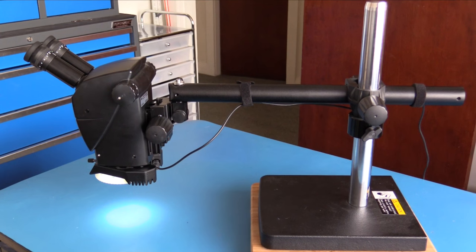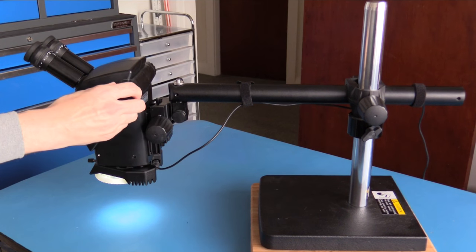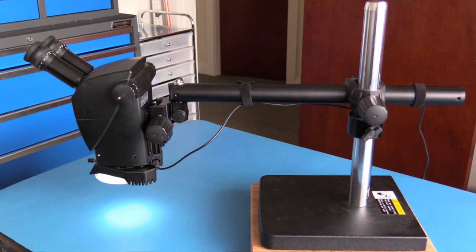This stereo microscope's optics are par focal. Par focal refers to the ability to focus this microscope and then adjust the zoom level. The microscope will remain in focus across the zoom range. This allows you to adjust the level of magnification without needing to refocus the microscope.